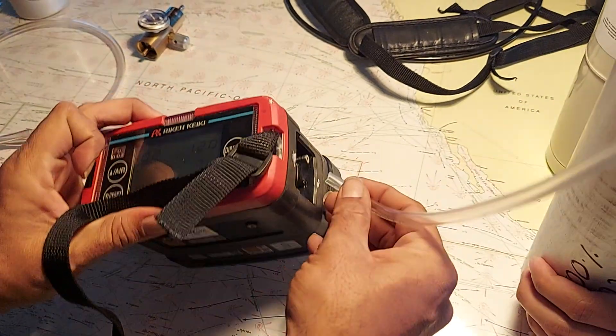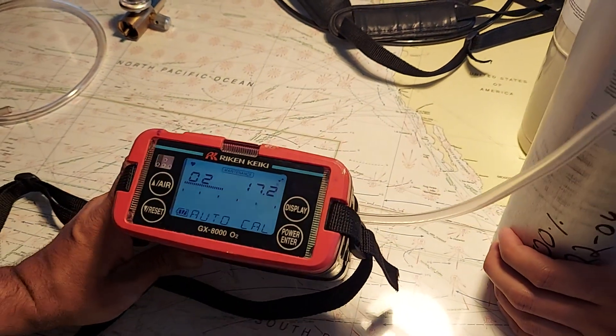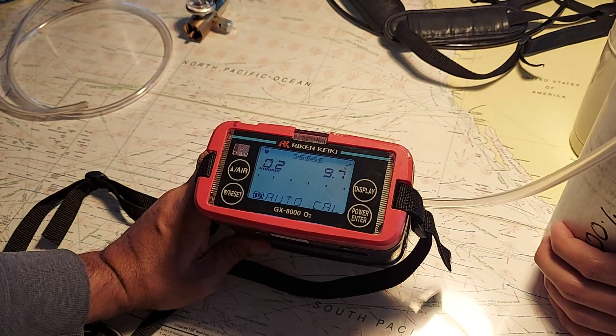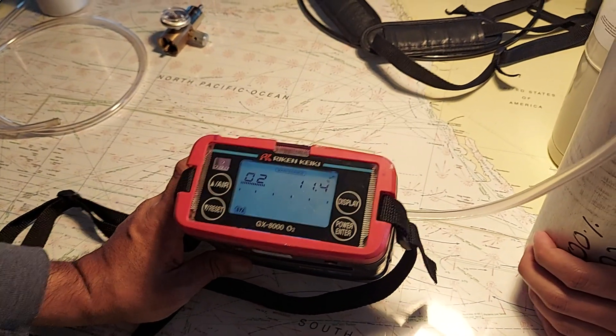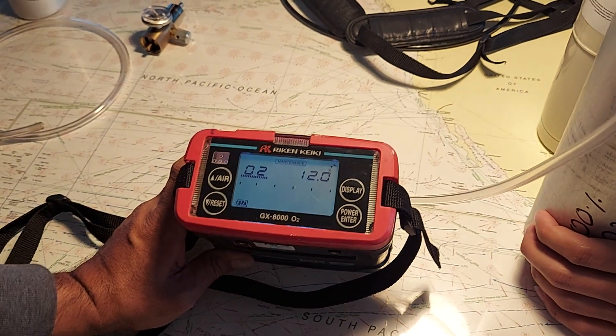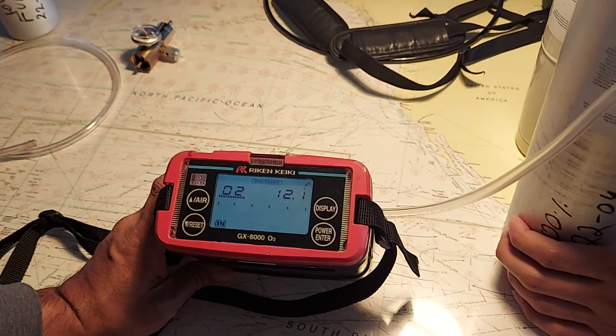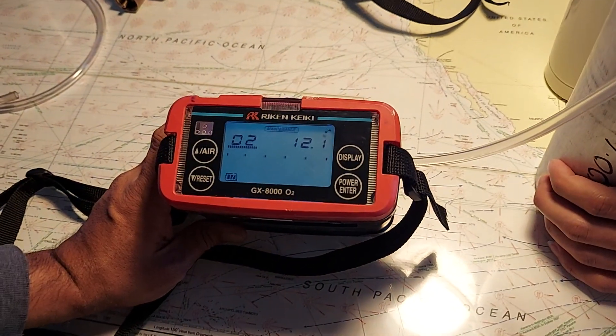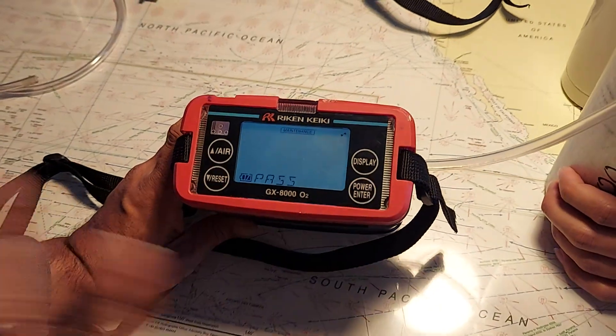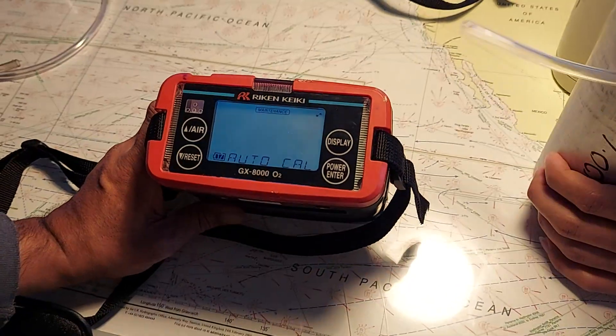Connect it to the suction side and press enter. Wait for the value to get steady. This is auto cal, which means we don't have to adjust the value — it will automatically adjust. The value is not changing now and it's steady at 12.1, so press enter and it has passed. Auto cal is done. We are done with the GX-8000 portable.